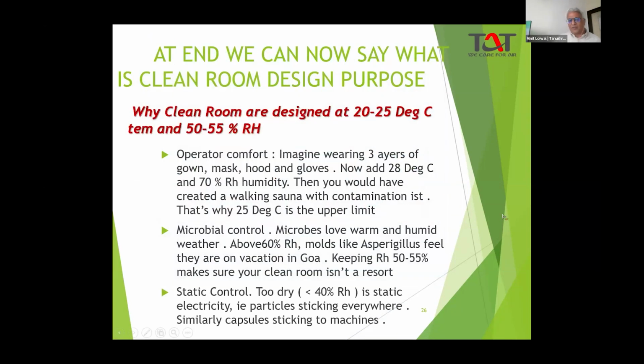Then at the end we can say what the clean room design purpose is. Why are clean rooms designed at 20 to 25 degrees centigrade and 50 to 55 RH? This is a thumb rule, basically for operator comfort. An operator is wearing three layers: gown, mask, hood, and gloves. If we set 28 degrees centigrade and 70% RH, you would have created a walking sauna, and he would not be able to sit there.